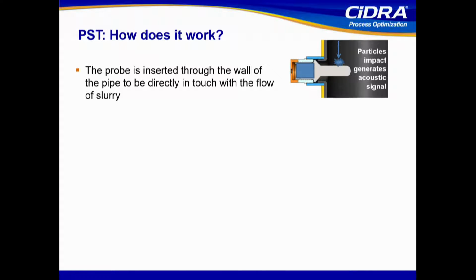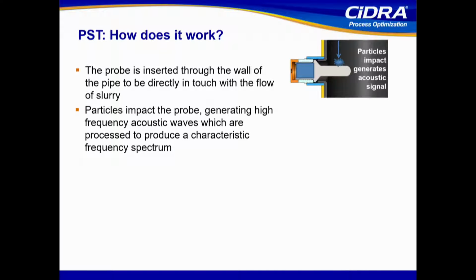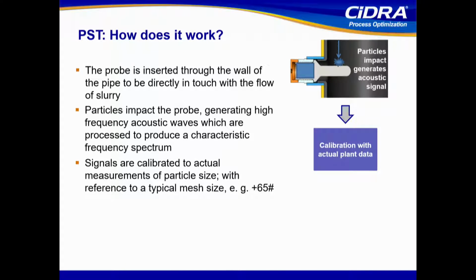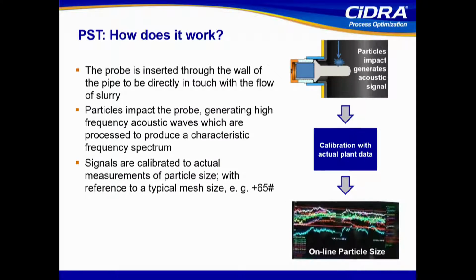The probe is inserted through the wall, and the particles simply hit the probe, and this impact generated by the particles is then interpreted as the particle size. Of course, to calibrate this, you will need to take samples with the actual variation range of the process operational conditions, and based on that you create a model for this, and when that is done you can utilize that model.